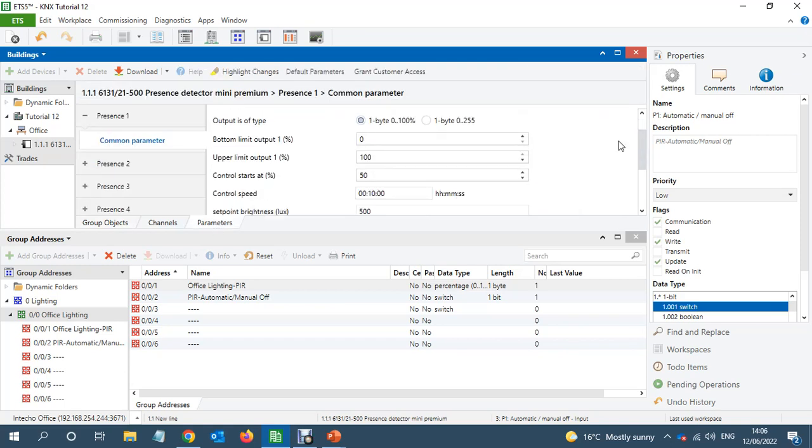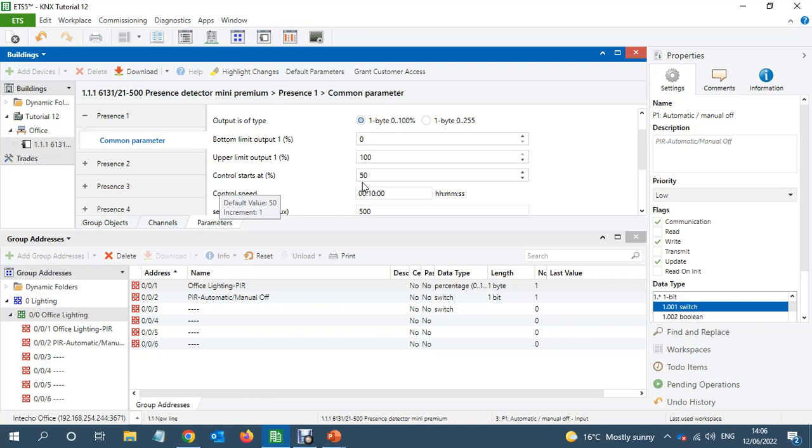The PIR will turn on the light at 50%, then it will calculate what the lux level is. If it's above 500 lux, then it will start decreasing.